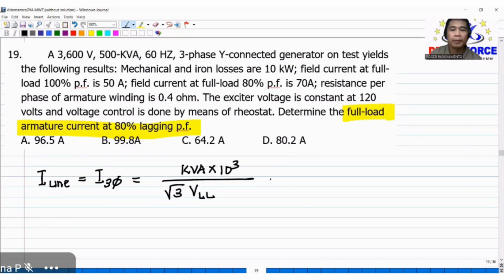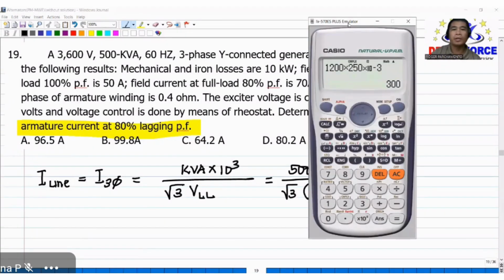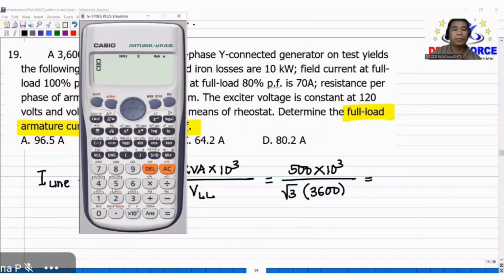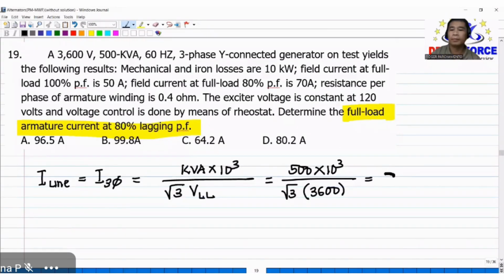So Y connected, the line value is also equal to the per phase current. So that will be 500 kVA times 10 to the 3, then divided by square root of 3 times the line-to-line voltage, which is 3600 volts. So the line current for this machine at full load is equivalent to 500 exponent 3 divided by square root of 3, then times 3600. So 80.2. So letter D.